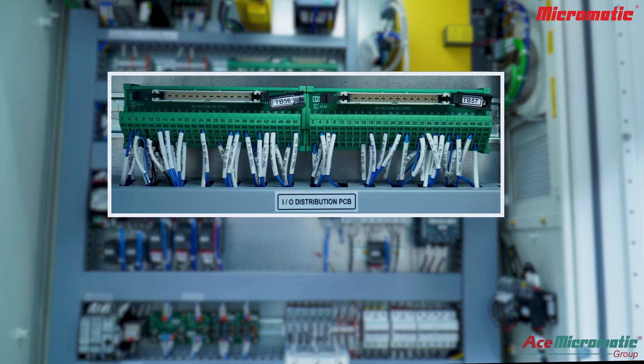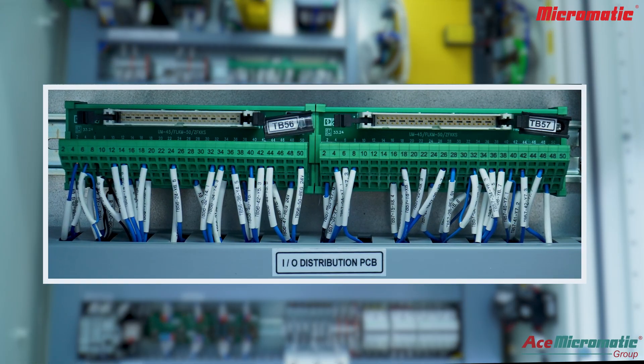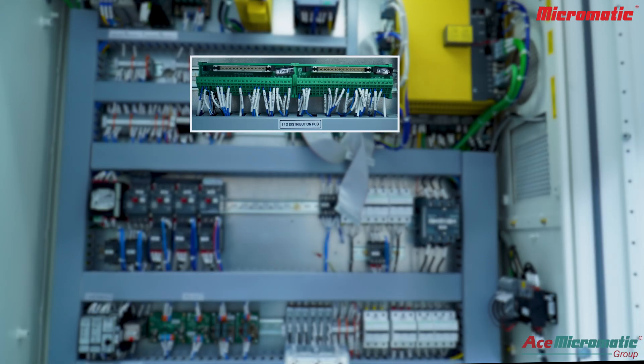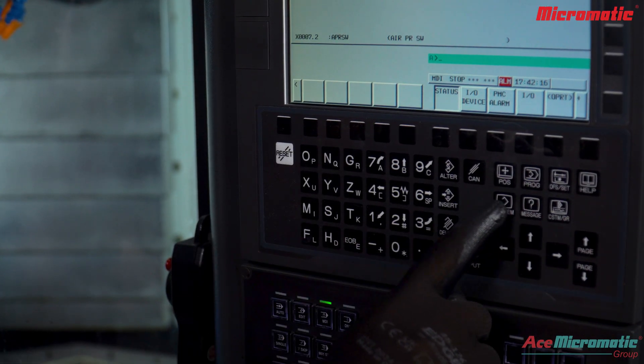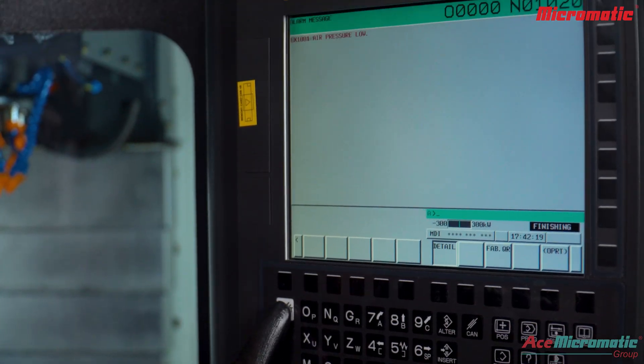Confirm pressure switch connection near terminal panel in electrical panel. When X7.2 becomes 1, the air pressure alarm will reset and normal operation will resume.